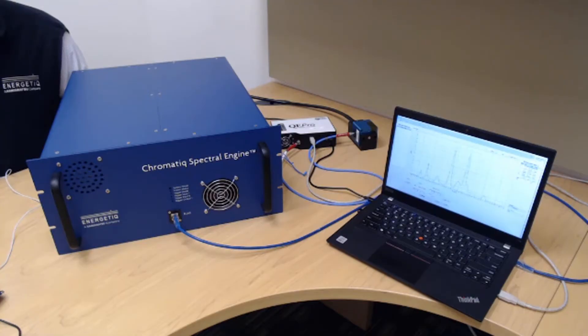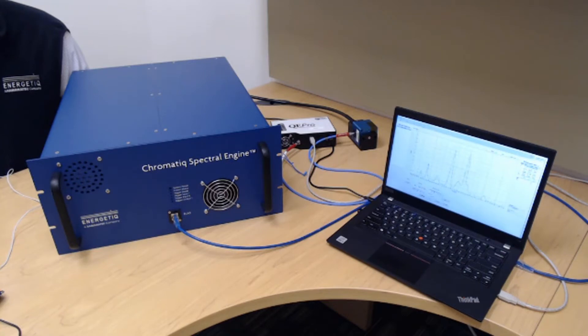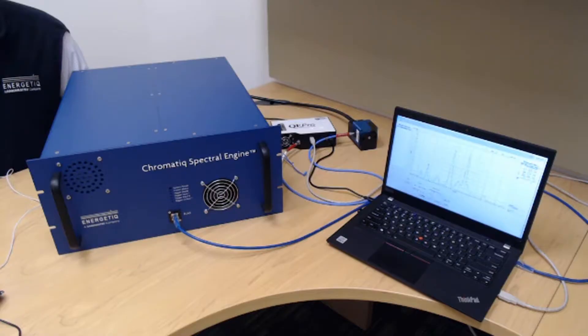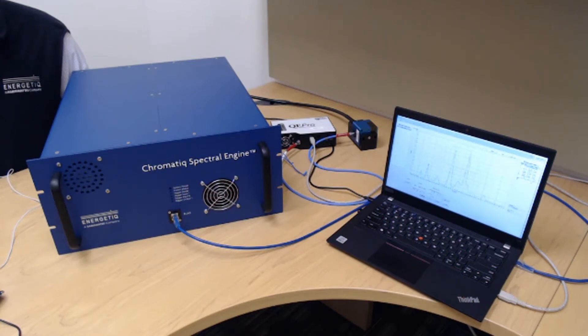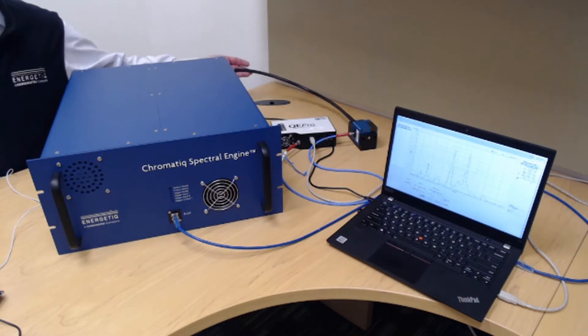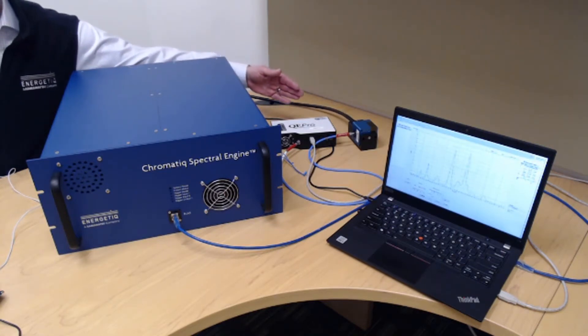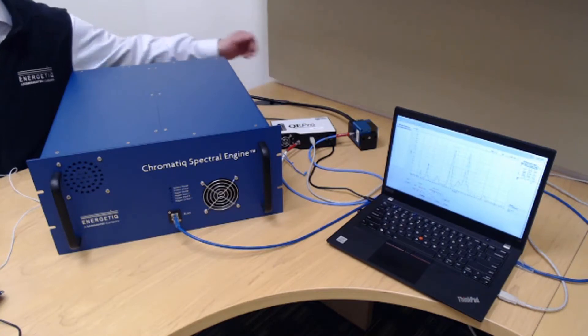Chromatiq Spectral Engine is an all-in-one standalone system. I'm showing the system connected to a spectrometer for matching of new target spectra. Once the targets are matched, they are stored in the Chromatiq Spectral Engine and can be recalled at any time without the need for feedback from the spectrometer. The output of the system is coupled into a liquid light guide. The liquid light guide is connected to an integration sphere and a spectrometer for the matching process.